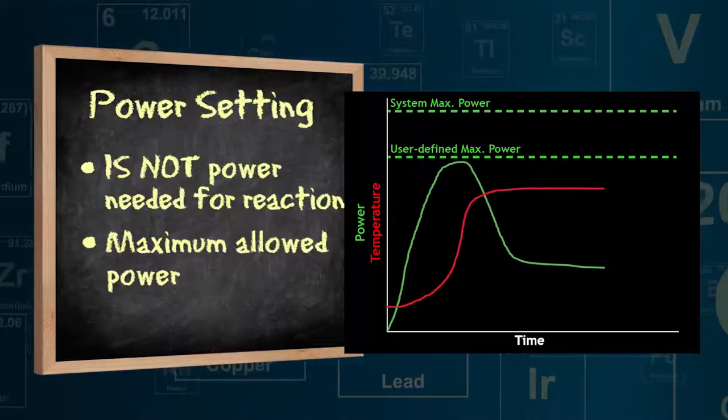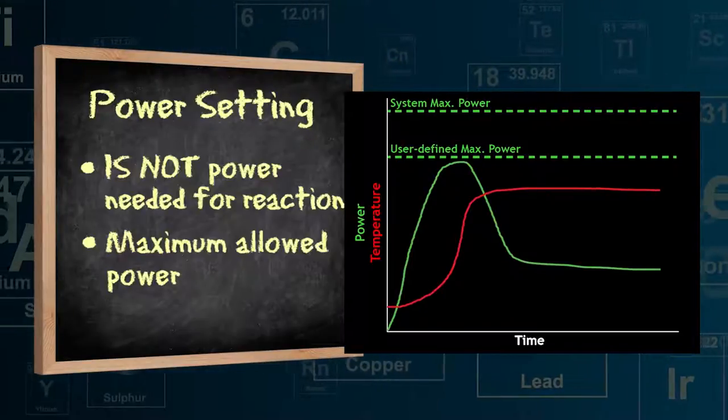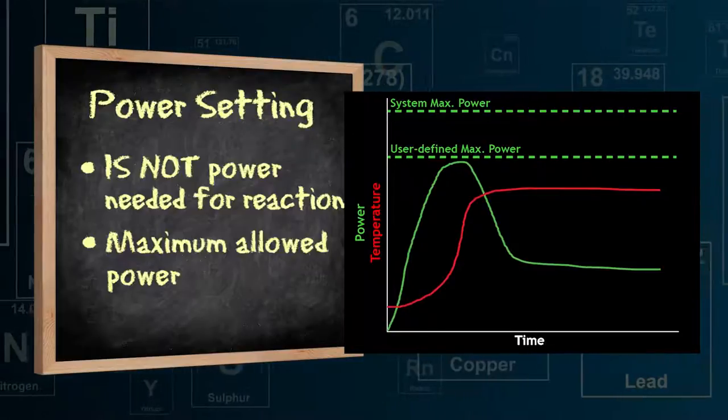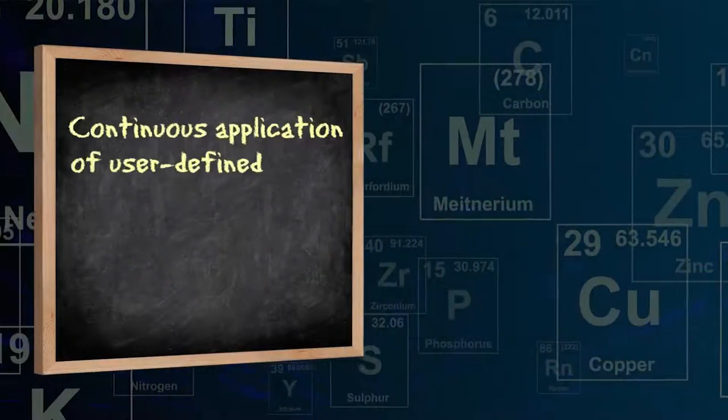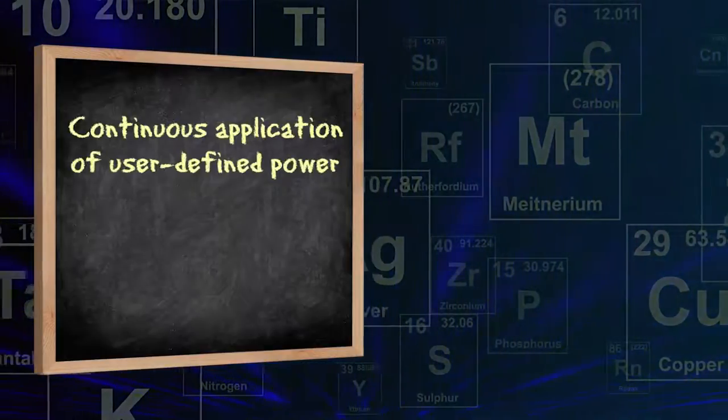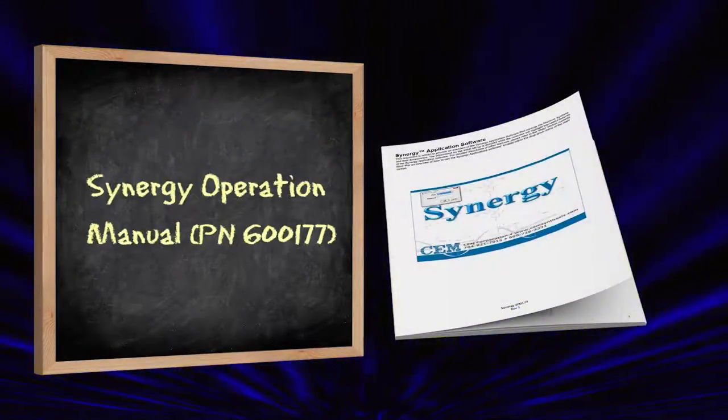You can see in this graph that greater power is necessary when ramping up to temperature, but after the reaction has begun, less power is required to maintain the temperature setpoint. CEM does offer power control modes which allow for continuous application of a user-defined power. See the Synergy operation manual for details.